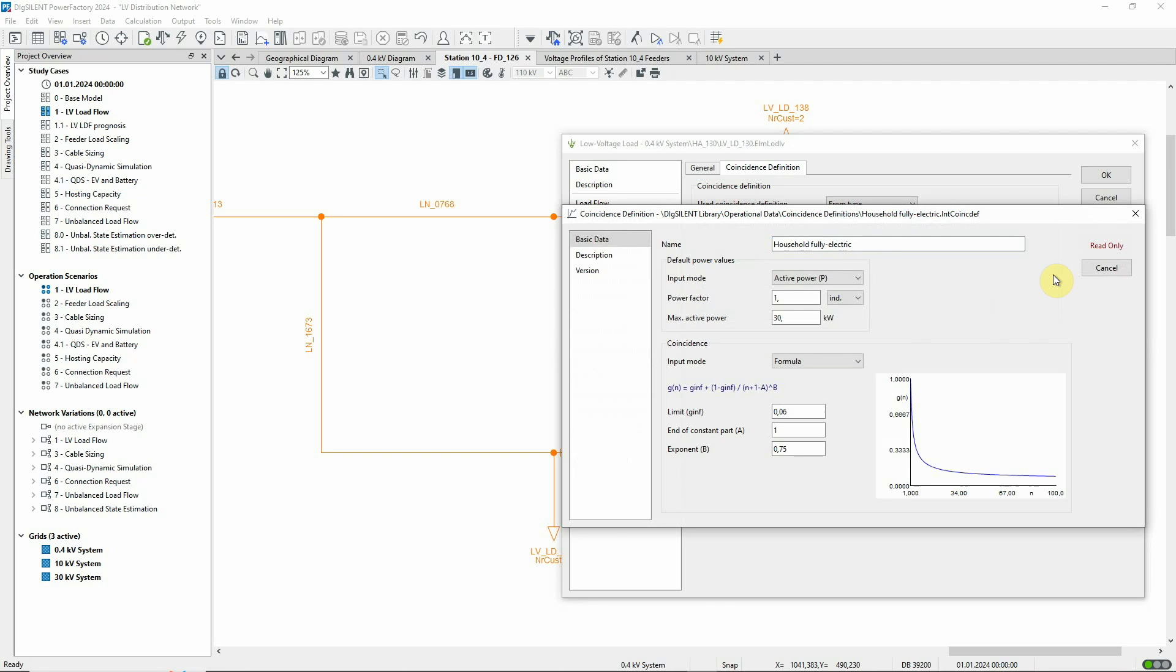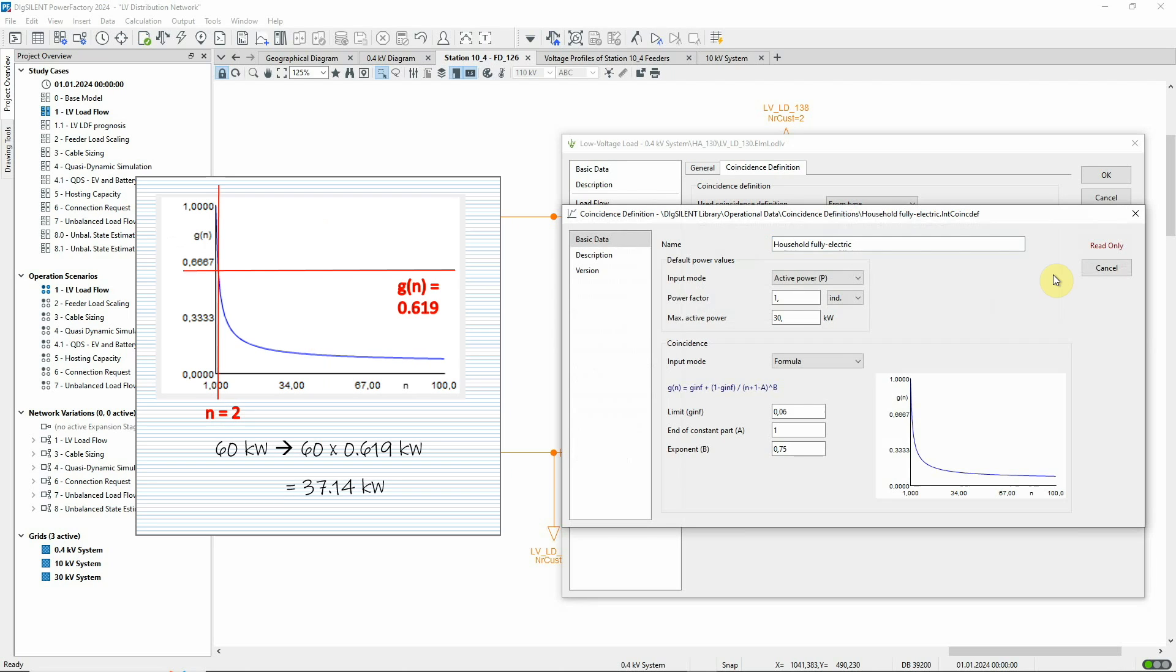This means that for this low voltage load element, although the simple arithmetical sum of the 30 kW would result in a 60 kW consumption for the network, the consideration of the coincidence curve already leads to a decrease to below 40 kW for these two units.